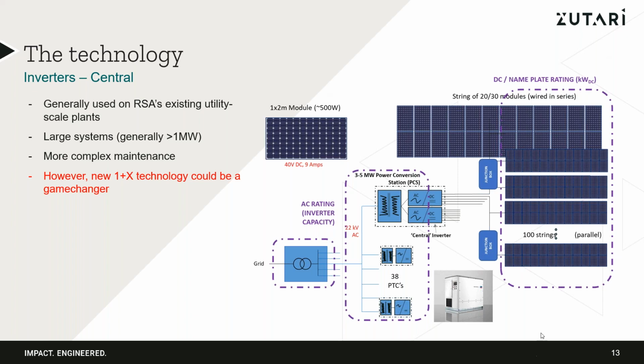The difference here is that you've got a very large DC network. So your strings, which are the PV modules organized in strings, run to a junction box or combiner box, where they're combined into what we call DC subarray cables. Those subarray cables then generally run in trenches to a central station, which is now called a power conversion station, not a power transformation kiosk.